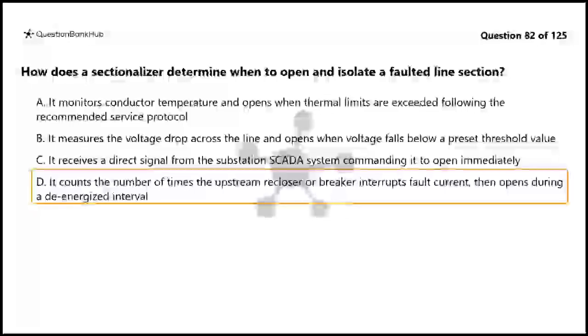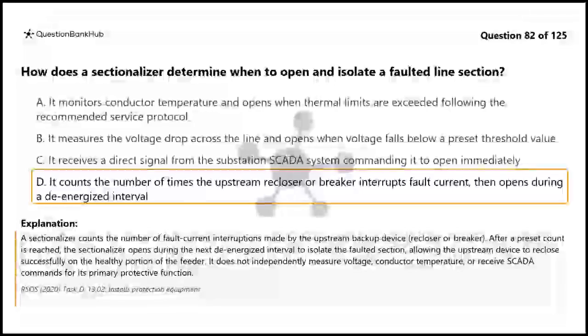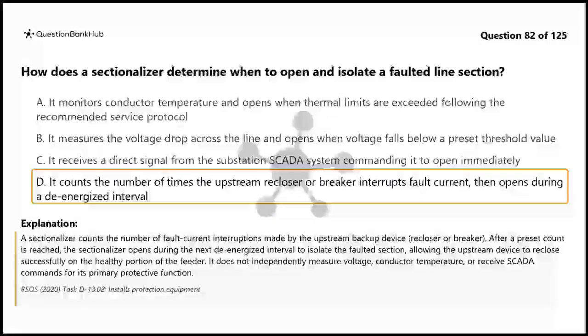The correct answer is D. A sectionalizer counts the number of fault current interruptions made by the upstream backup device, recloser or breaker. After a preset count is reached, the sectionalizer opens during the next de-energized interval to isolate the faulted section, allowing the upstream device to reclose successfully on the healthy portion of the feeder. It does not independently measure voltage, conductor temperature, or receive SCADA commands for its primary protective function.